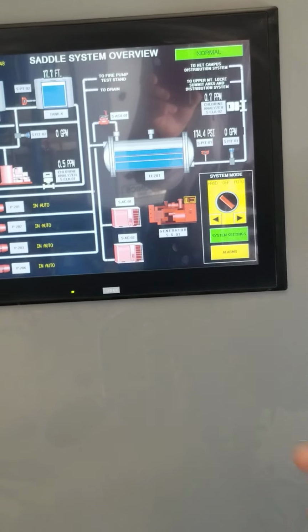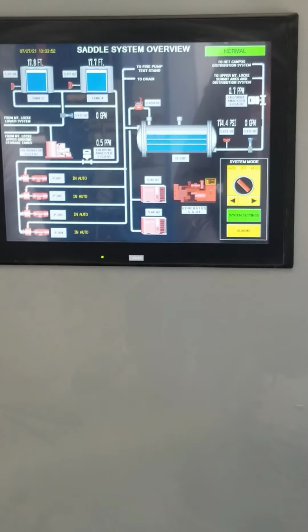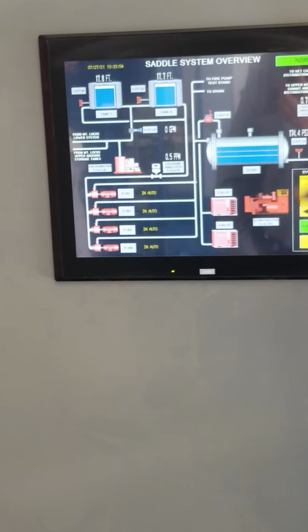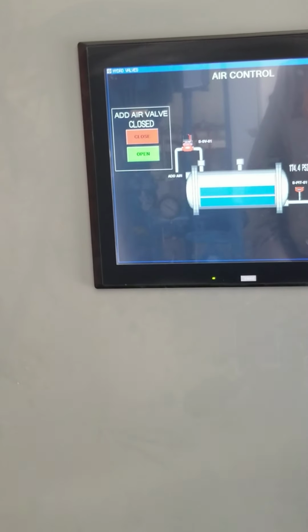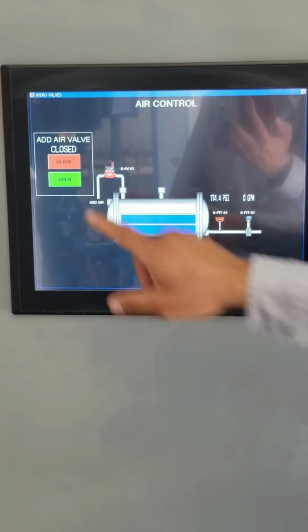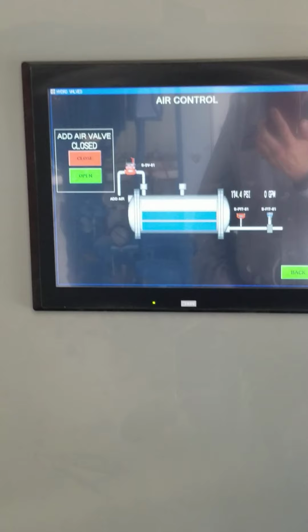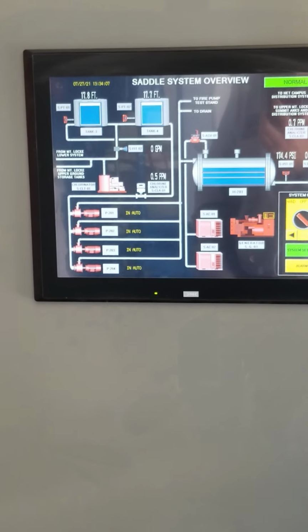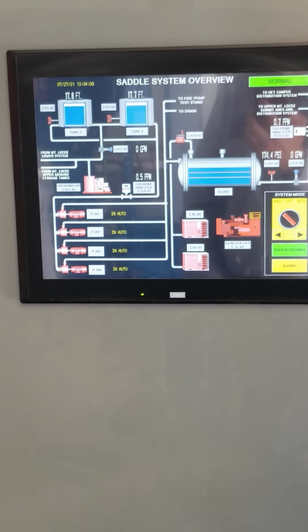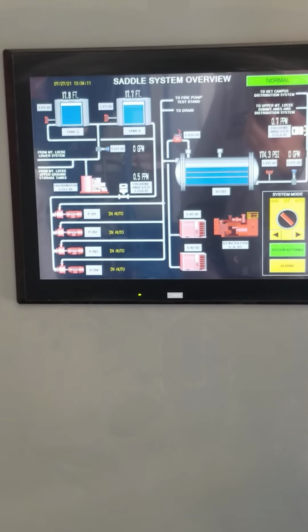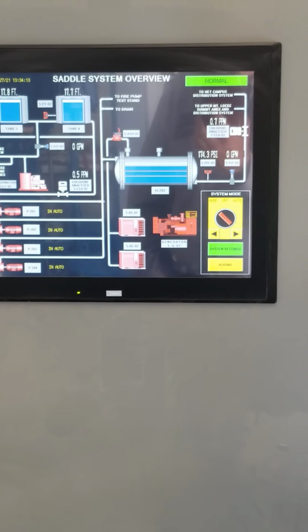Same thing on the chlorinators, they are standalone. I mean, the compressor runs by itself. Yeah, there's nothing there. That's why they won't take it to a screen. Also, here's a screen for the hydro tank and operating the solenoid, so you can open and close it. There you go. Sure. And hand mode. That will only work in hand mode. That's about it. Everything else, there's no hand operation other than a standalone system.